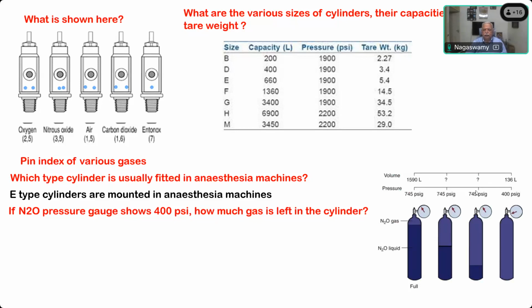Until then, it will be showing the same pressure. So when the pressure roughly becomes half of the initial pressure, from 1600 liters the gas will be only 136 liters. This matters if a patient is undergoing neurosurgery and you are using nitrous oxide. Nowadays, of course, nitrous oxide is being condemned for usage and people have started using only medical air. But earlier, when they were using nitrous oxide, the plane of anesthesia would vary and the patient could become lighter. Similarly, in cardiac surgery also, there may be a lighter plane of anesthesia. If you do not know what the pressure is and how long the nitrous oxide cylinder will last, the patient is likely to receive a lighter mixture and become lighter in plane of anesthesia. That is the reason why they incorporated this.